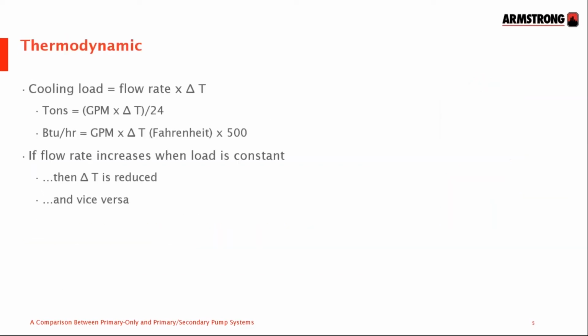Now, before we get into this, to help us understand the system slides better, it's best that we remind ourselves that the cooling load of a system is equal to the flow rate of water through that system times the delta T, the rise or the fall in temperature. This is the most important formula to know because at a constant load, if the delta T is reduced, then the flow rate must go up to compensate for that cooling load. If the delta T goes up, the flow rate must go down. We'll be coming across this when we get into slides later on.